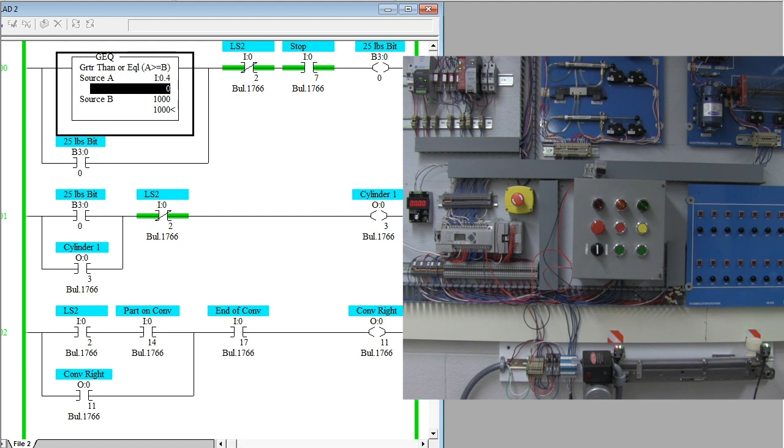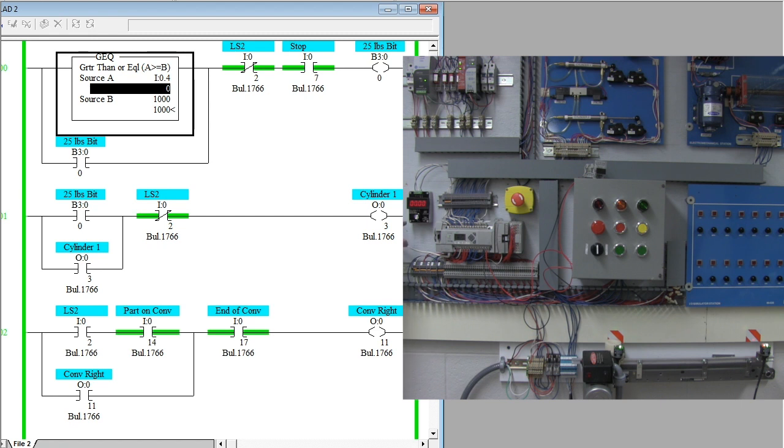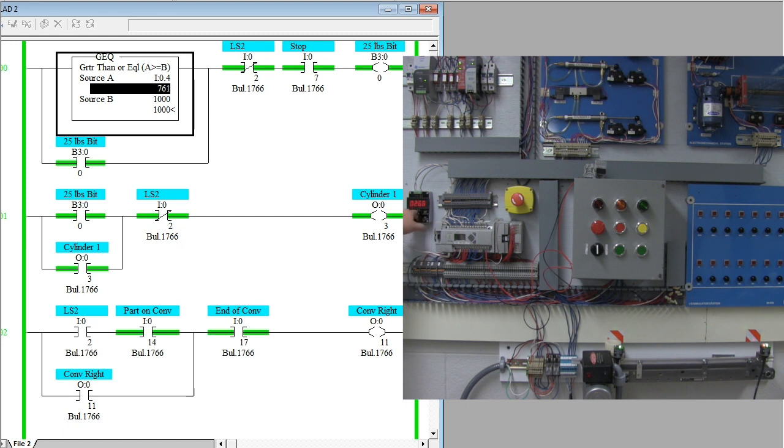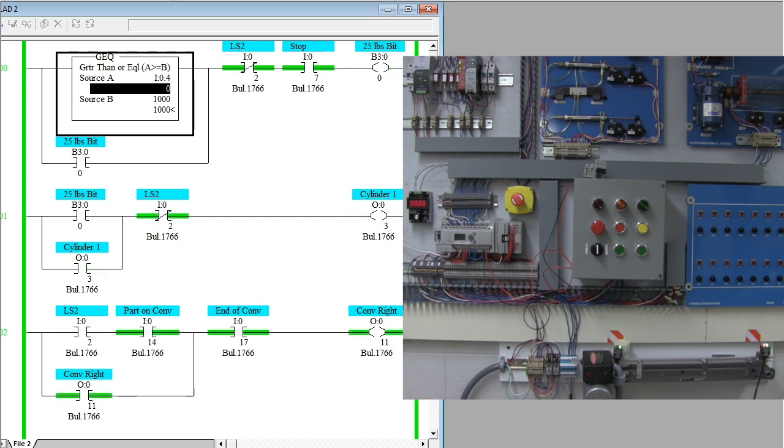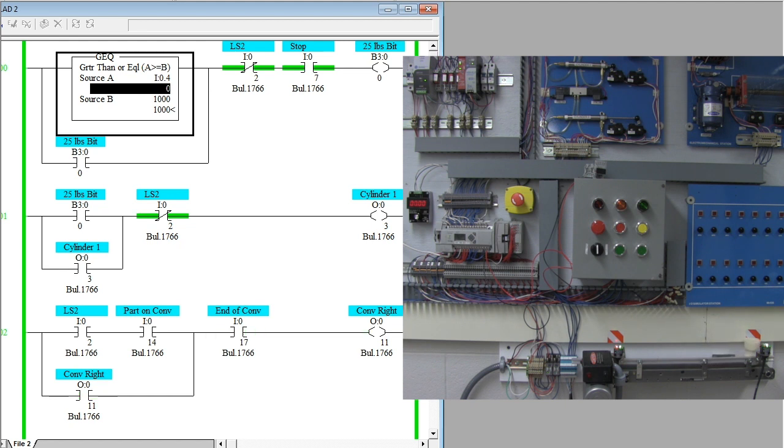Let's go ahead and walk through that one more time. I'm going to simulate 25 pounds of a product being put onto a strain gauge. When that 25 pounds is there, the cylinder extends. When it's all the way extended and the part is right on the conveyor, the conveyor moves. At the end of the conveyor, the conveyor stops and the process is ready to rock and roll one more time.